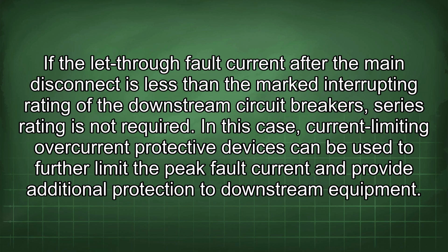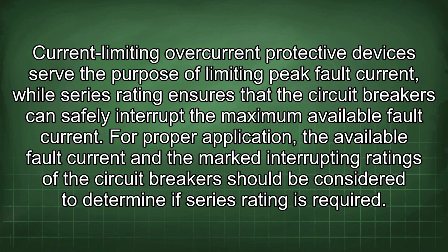In this case, current-limiting overcurrent protective devices can be used to further limit the peak fault current and provide additional protection to downstream equipment. Current-limiting overcurrent protective devices serve the purpose of limiting peak fault current, while series rating ensures that the circuit breakers can safely interrupt the maximum available fault current. For proper application, the available fault current and the marked interrupting ratings of the circuit breakers should be considered to determine if series rating is required.